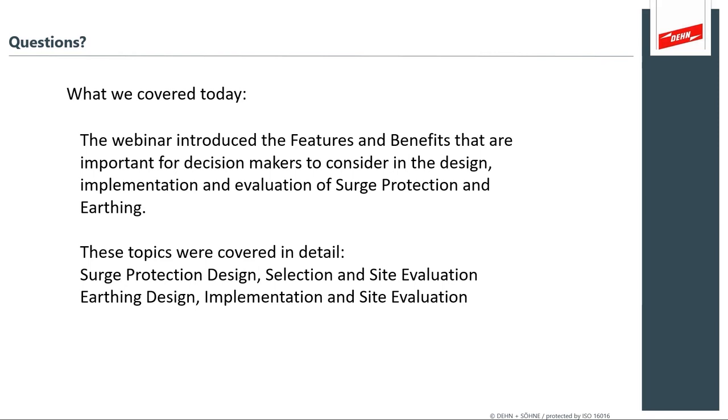Yeah, so in other words, if I can just say back what you're saying, the voltage protection level that a surge protection device provides for an installation is not just the rating across the SPD, but it includes the conductor that's run from the phase to the SPD and from the SPD to ground. That's the whole voltage protection level between line and ground that the equipment is going to see. So the sum of the voltage drop over the wire from phase to SPD, the voltage protection level of the SPD, as well as the voltage drop over the wire from the SPD to ground, that sum will be the final voltage that your equipment will see.